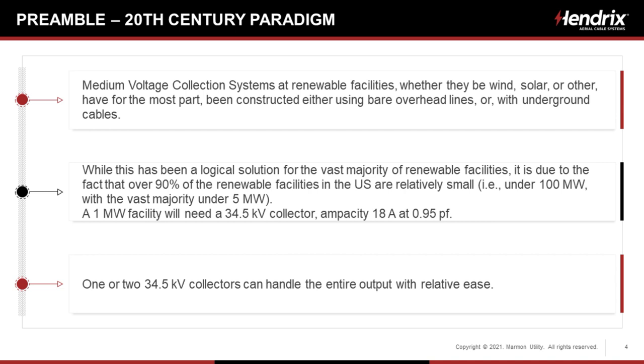For the preamble, I call this kind of a 20th century paradigm. When you take a look at medium voltage collection systems at renewable facilities, whether wind, solar, or other, for the most part they've been constructed using either bare wire overhead lines or underground cables. There's been a logical solution, bare wire or underground cable, for the vast majority of renewables facilities. It's due to the fact that 90, probably 90 to 95 percent of those facilities in the U.S. are relatively small. They might be 100 kilowatts, 500 kilowatts, 1 megawatt. I'm saying they're under 100, but the vast 95, 96, 97 percent of these facilities are under 5 megawatts.